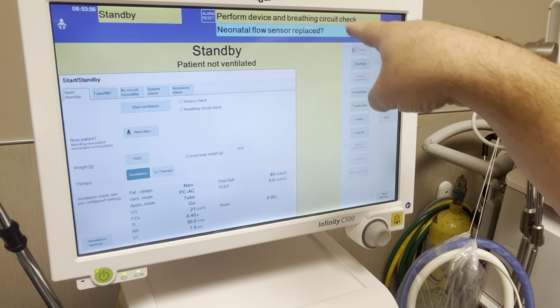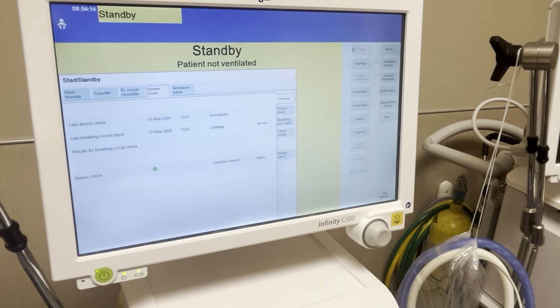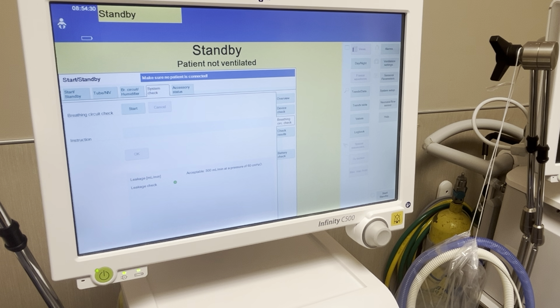All right, so when the rep came out here to tell us, they gave us a trick and told us to start with the breathing circuit check, even though the device check will tell you to do the breathing circuit check afterwards. The device check will fail if your circuit's not set up right or if it has any leaks. So it's kind of better to do the circuit check first.